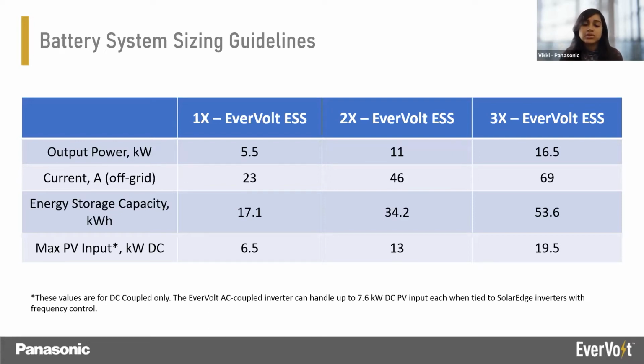So it's very, very important to be mindful of not exceeding the limits of the PV sizing here. It is typical practice in the industry to oversize PV inverters by a certain percentage. But with battery systems, it becomes tricky because we don't want to overcharge the batteries in an off-grid situation. And that's why for DC coupled systems, it's 6.5. The good thing about AC coupled system is with frequency load control, or by balancing the number of microinverters connected to the battery system, we can go slightly higher than this. So with SolarEdge inverter, when it's tied to the AC coupled unit, we can go as high as 7.6 kilowatts.